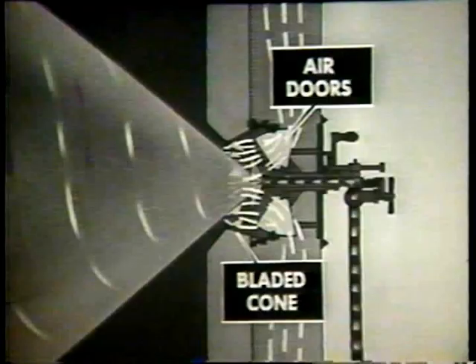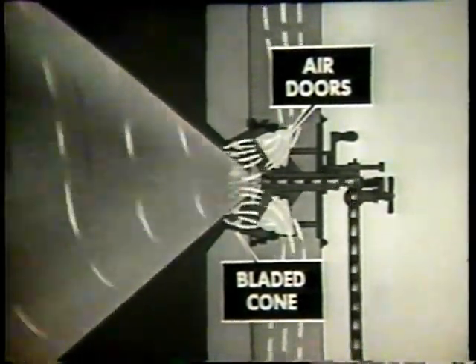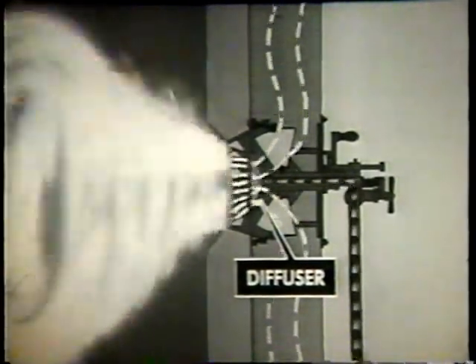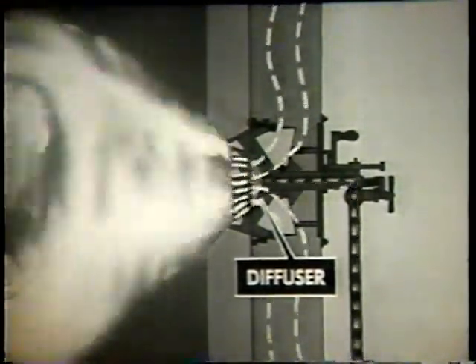Meanwhile, in the burner register, air provided by the force draft blower is given a rapid rotating motion by the air doors and bladed cone and mixed with the oil spray. The mixture of oil and air enters the furnace where combustion takes place. The diffuser prevents the air blast from blowing the flame from the atomizer tip.